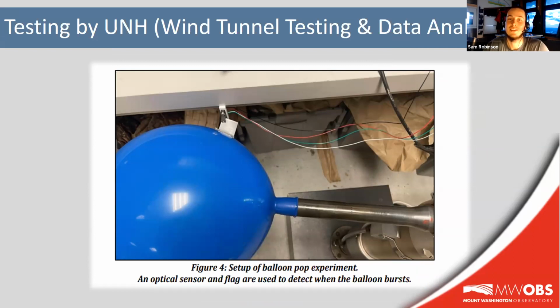So in more technical terms, it is desirable to determine the transducer's transient response characteristics. And this balloon pop test is basically going to provide that needed input to produce this. And it was found that the sensors do experience a little bit of overshoot and oscillation before they eventually damp out to a steady measurement. So there's a little bit of resonance there. Through a series of very technical formulas and extensive calculations, it was found that the settling time for the 0 to 10 transducer was 69 milliseconds, and then 56 milliseconds for the 0 to 70 inch transducer. And the overshoot percentage was found to be 144% for the 0 to 10, and then 153% for the 0 to 70.